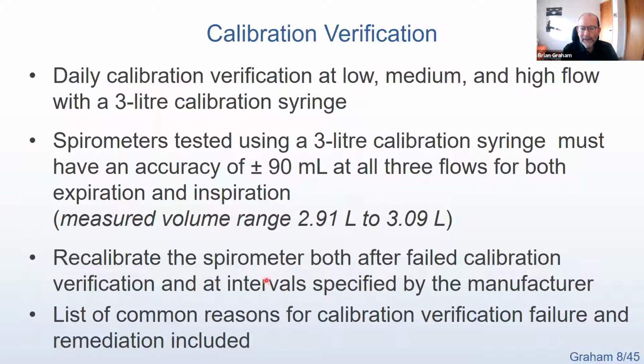If the spirometer fails the calibration verification, then of course you need to recalibrate. Recalibration is also required by some manufacturers at various intervals, so that at least weekly there has to be a recalibration. In the standards, we've also included a list of some of the common reasons for calibration verification failure, and what actions you can take if you do fail the calibration verification.